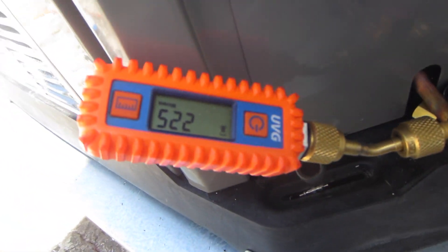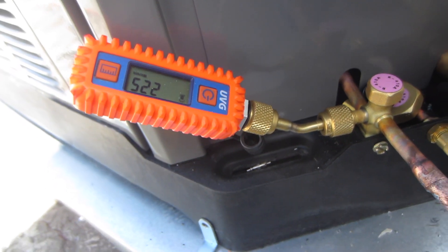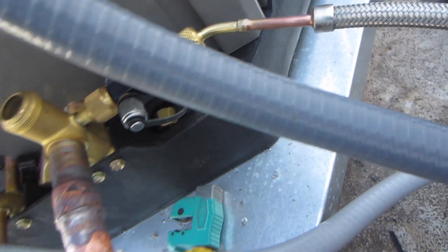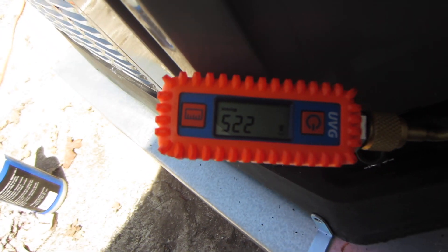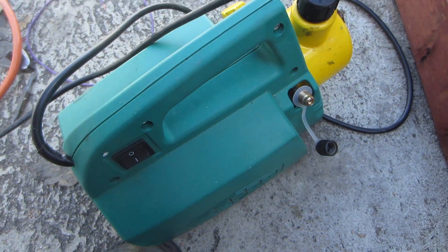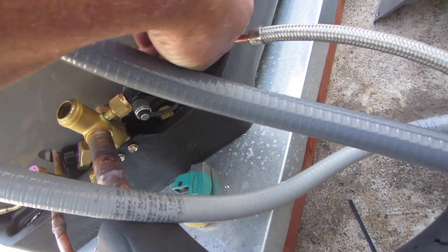My vacuum is down to 522 microns — single hose application. Make sure it doesn't rise. 1.35 CFM — that's all it takes.